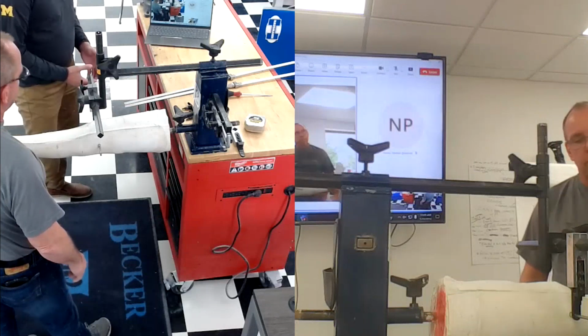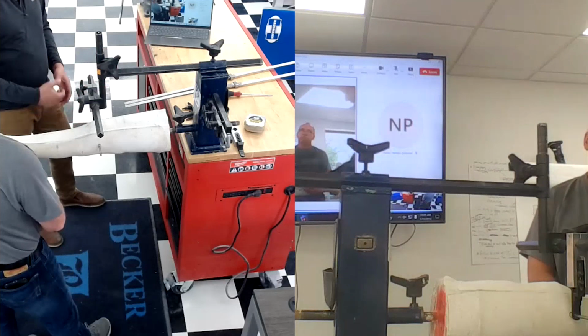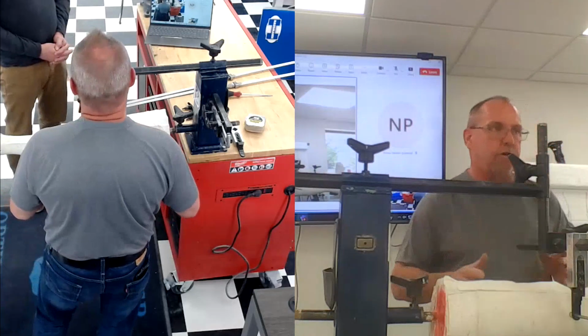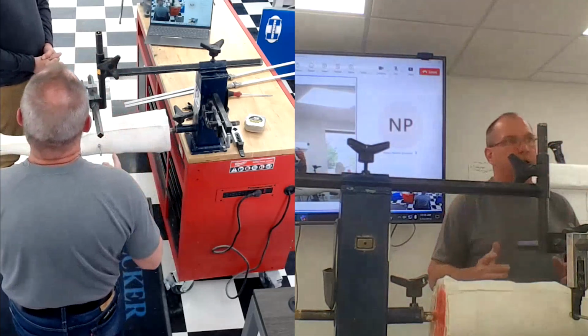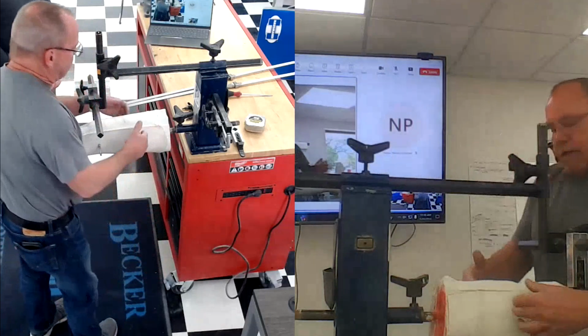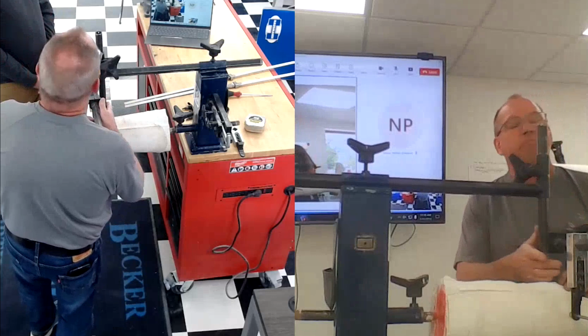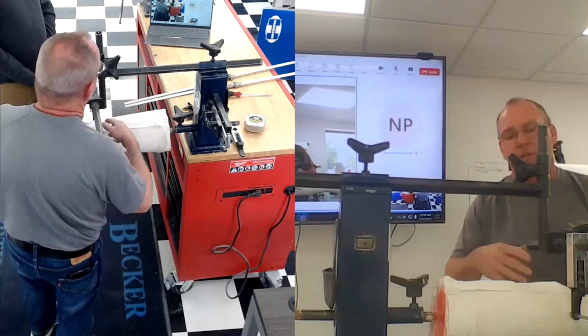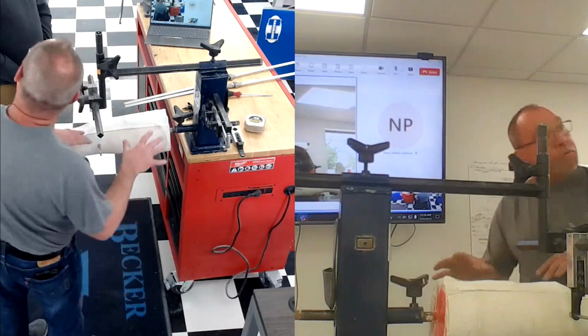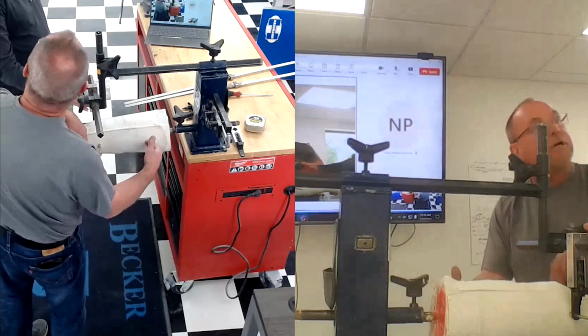In the case where you're doing a below-knee prosthesis with a corset, we have to think about how to do that differently when we can't drill a rod through our mold. There's going to be a couple of different things. Basically we have to have an identifying marker and a distance from that marker to what we're going to consider the articulation zone. Once we've identified that and put the marker on, I would then build out a mold wedge, a lot of times just a piece of wood that would go up against this rod where it would meet up in distance from that identifying marker to the articulation center.